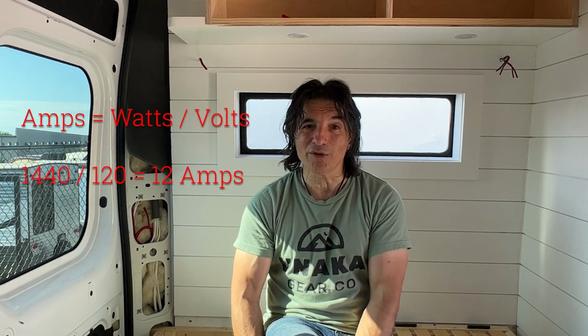Now that one gets up to 1440 watts. Again, we divide that by 120 volts and we get 12 amps. So with that one we could safely run on a 15 amp breaker. So what we're going to have is a 20 amp breaker and a 15 amp breaker. Now if you do the math, you're going to realize that just those two devices can get us up to 27 amps out of our possible 30. So we just have to know that we probably will not run those two devices together.